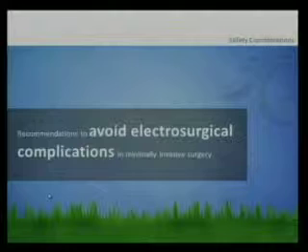So what I've read is that the hole in the glove is not why you get the injury. It's not a pre-existing hole. The hole is created when you have the arcing and the stray current. So a hole in your glove is not going to make it so that you get an injury when you're buzzing a hemostat. So everybody use cut.